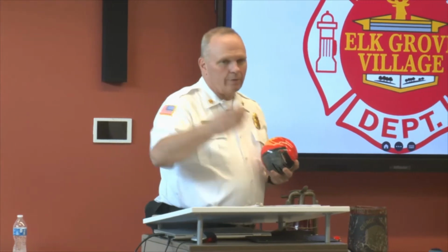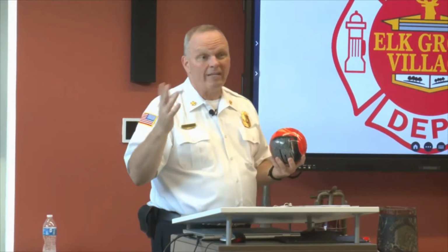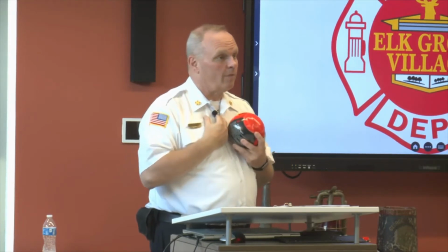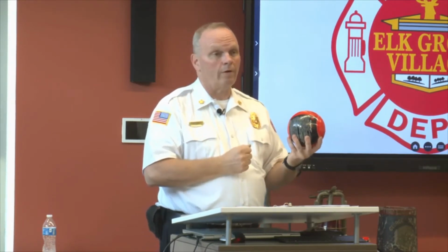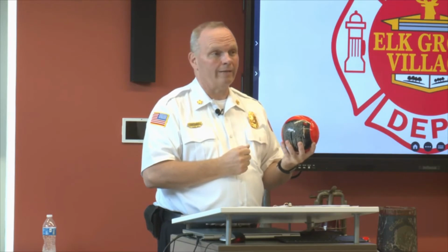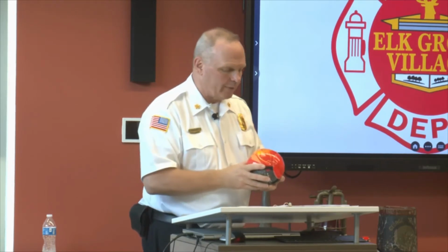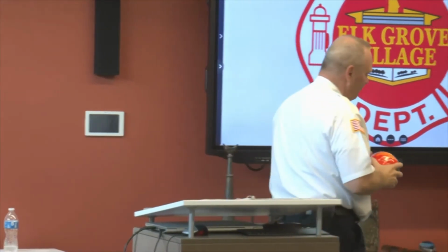Another point to consider: a fire sprinkler discharges about 15 gallons of water a minute, give or take. When our folks come with a nozzle, that's going to give you 200 gallons of water a minute. So we have to think about water damage that way too. We're anxious to give this a try.